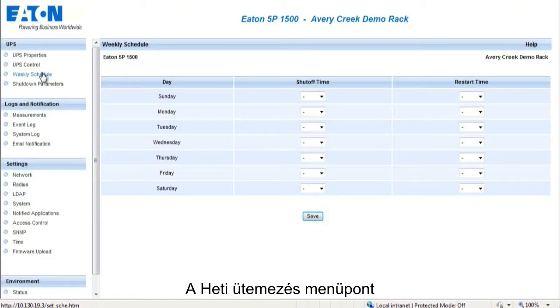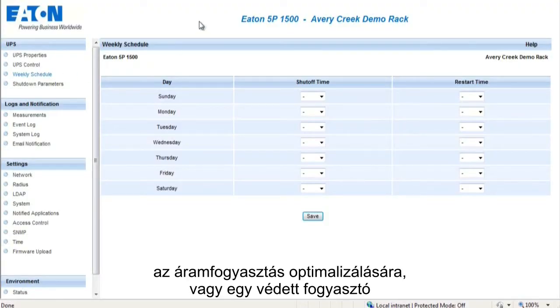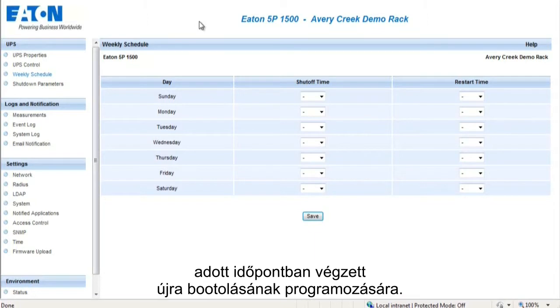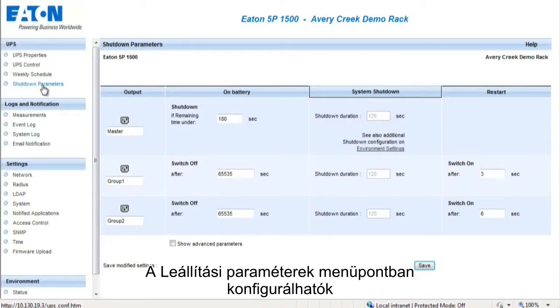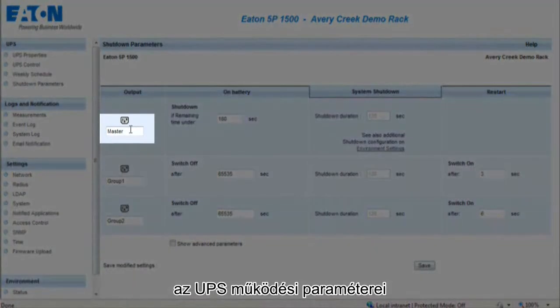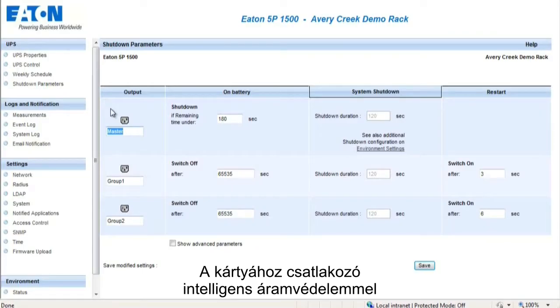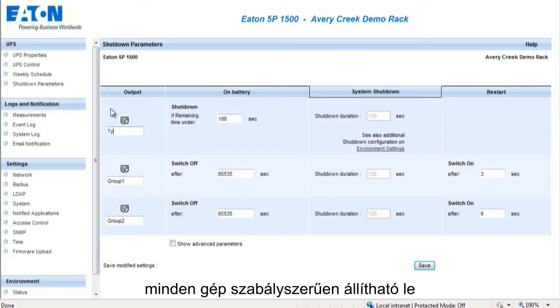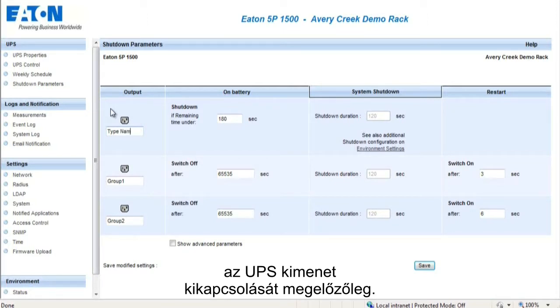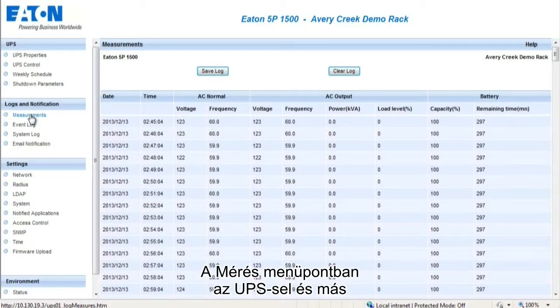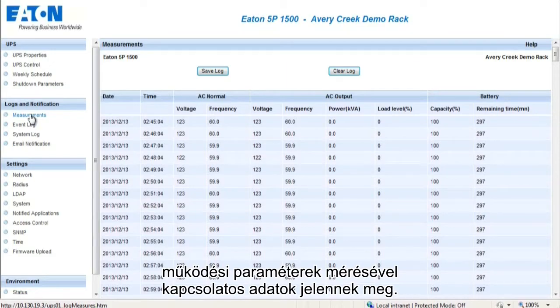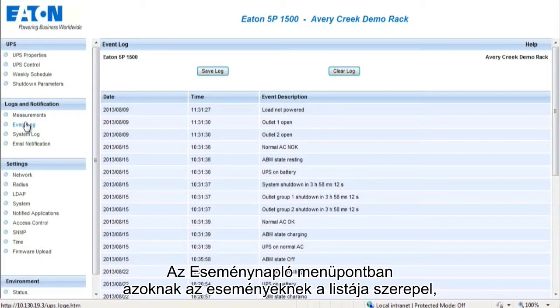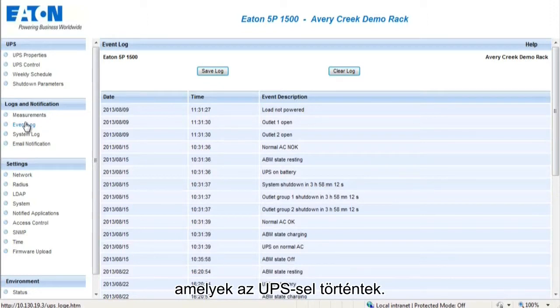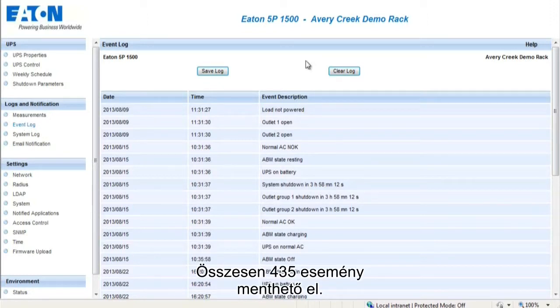The Weekly Schedule section provides the administrator the ability to optimize power consumption or program a reboot of protected equipment at a designated time. The Shutdown Parameters section allows the configuration of the UPS operating parameters in battery mode and for power restoration. With Intelligent Power Protector connected to the card, each machine is properly shut down before the UPS output is turned off. The Measurements section displays details concerning the UPS and other operating measurements. The Event Logs section provides a record of the events experienced by the UPS. A total of 435 events can be saved.